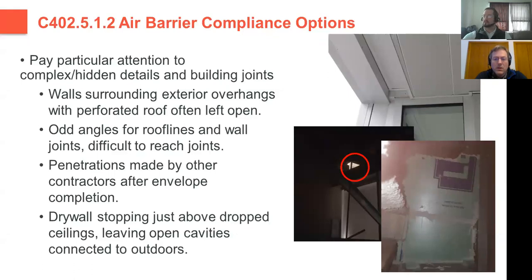and drop ceiling interiors. What we found was there's an I-beam that supports the outside rain screen structure, and I-beams that support the floor above on the inside. Between those, right above these patio openings, was an opening. And this was causing all sorts of issues with the HVAC system not being able to keep up. They had humidity issues in the summertime and heating and cooling issues year-round where they couldn't keep up with demand. Sealing those holes up fixed that problem.